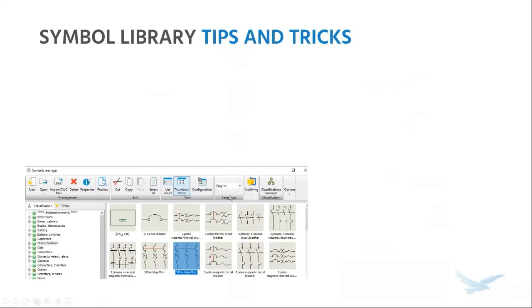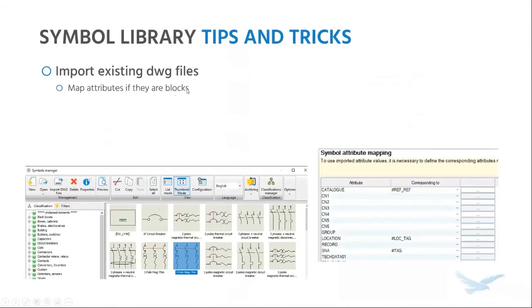I do have a few tips and tricks for the symbol library. Out of the box, SolidWorks Electrical comes with a whole bunch of symbols spread across different classes. But if you do have custom symbols created, you can import existing DWG files. If these DWG files happen to be blocks and they have attributes in them already, you get the opportunity to map those attributes to SolidWorks Electrical counterparts. Just like with title blocks, make sure that these symbols are created in model space, not paper space, in their DWG files.